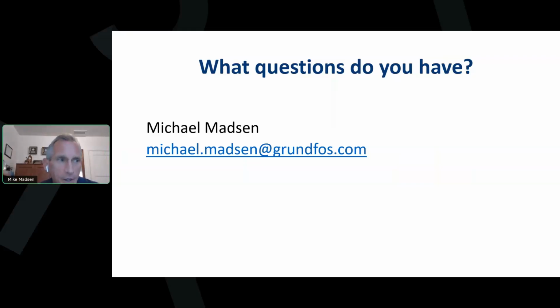It's a great question. On a control valve system, we're taking that leaving air temperature sensor and sending it back to the BMS system, and then the BMS system is telling the valve what position it wants. With us, we're doing direct control. We're taking that leaving air temperature sensor and sending it into the smart pump, directly controlling to leaving air temperature. We can still send data back to the BMS. Another nice thing, we have a single point RS-485 connection. So over a single connection back to the BMS, I can send any of that data that I want.